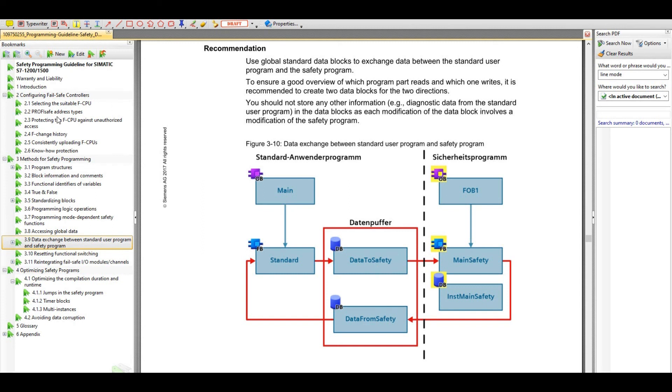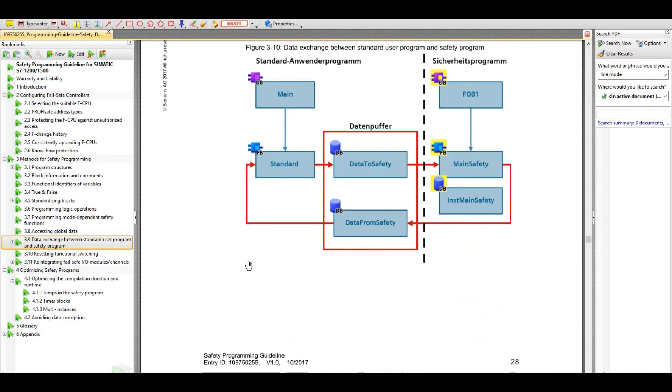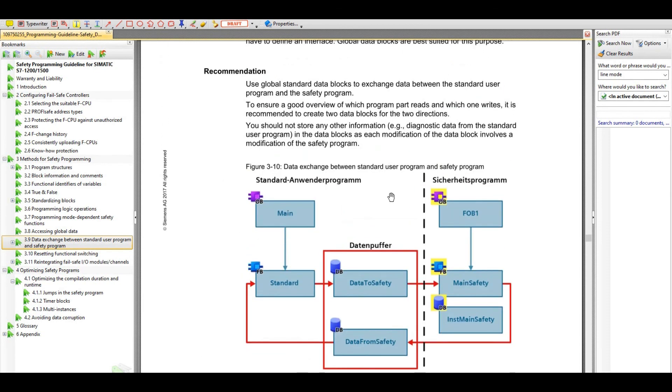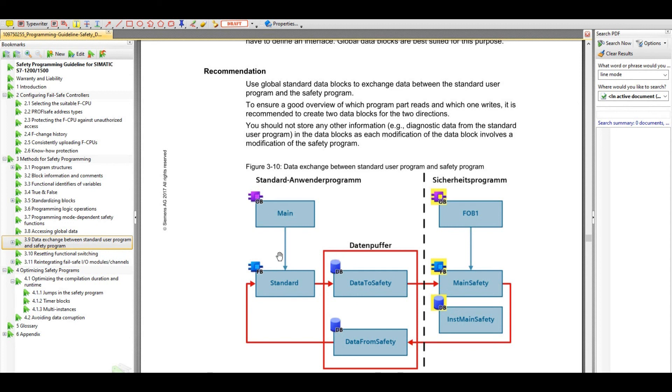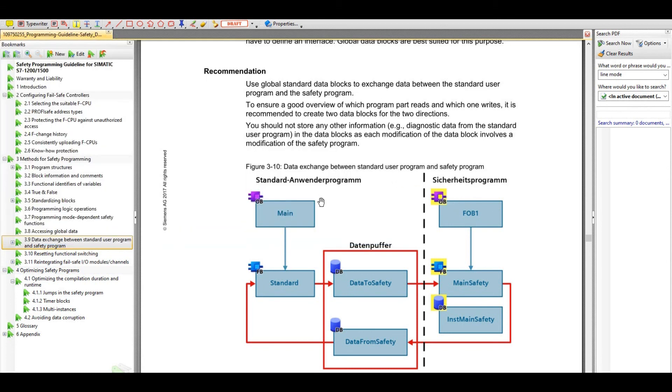Regarding this guideline, it has a lot of rich information. Before you program the safety logic, I highly recommend you better read this. We know the Beckhoff system and the Omron system, they all have some settings in the software. Basically, that setting plays a role on this interface portion. For the new starter, it is a little bit annoying because you need to transfer the data to that buffer area. In the safety, you need to grab this interface tags to the safety. However, with this interface, even if your standard logic change, there's no any impacts on this safety logic. The same is, you can use this tag very flexible. However, to prevent this difference issue, we better create two interface DB.